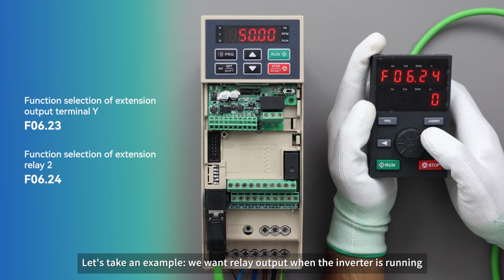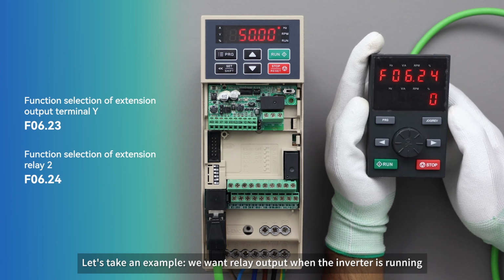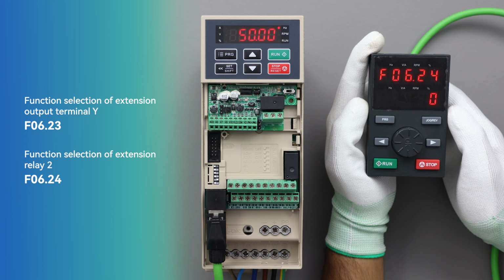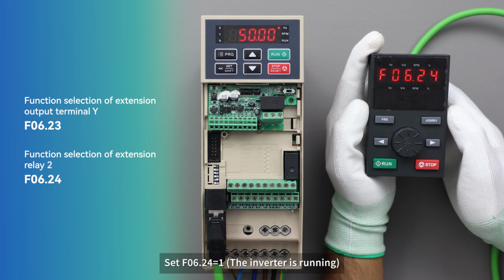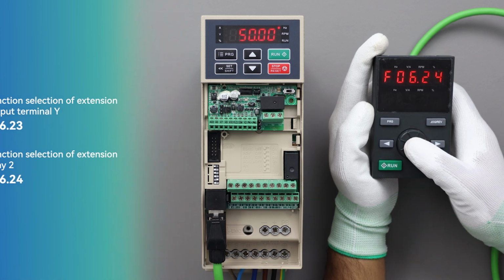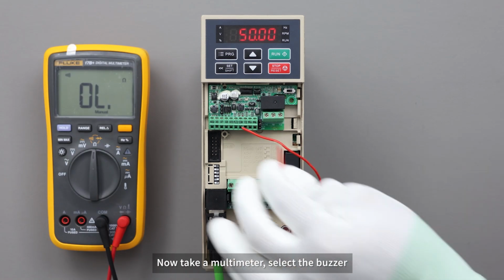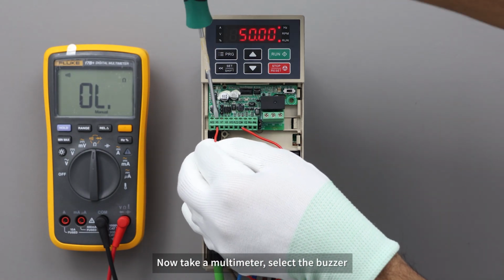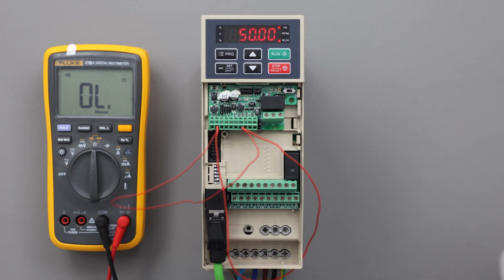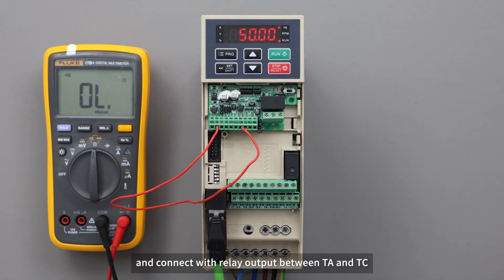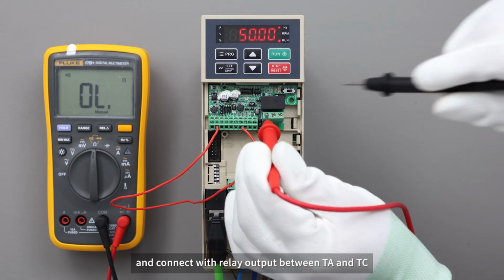Let's take an example. We want to relay output when the inverter is running. Set F06.24 to 1. Now take a multimeter, select the buzzer and connect with relay output between TA and TC.